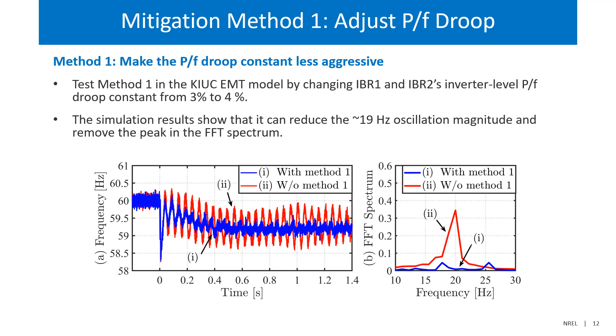After we changed it, the blue line shows the result after the control parameter adjustment. We could see that it mitigated the issue and removed the peak when analyzed with FFT analysis. This was the first thing we did.